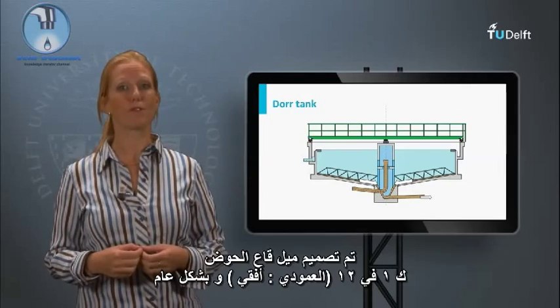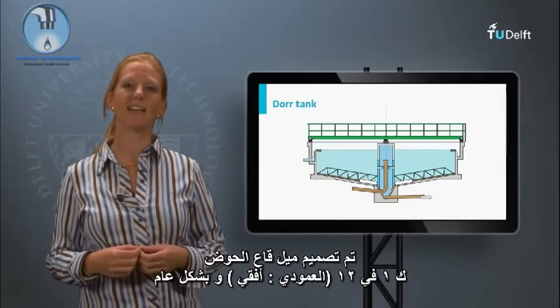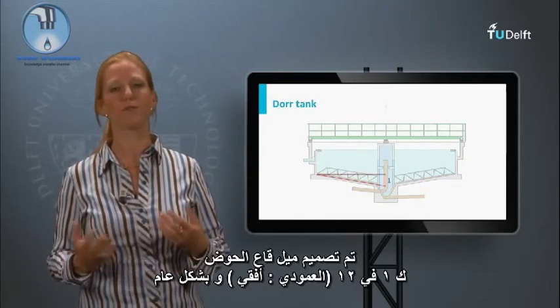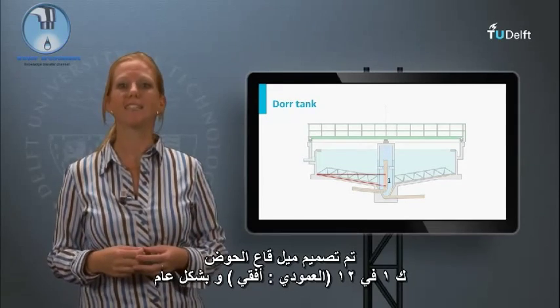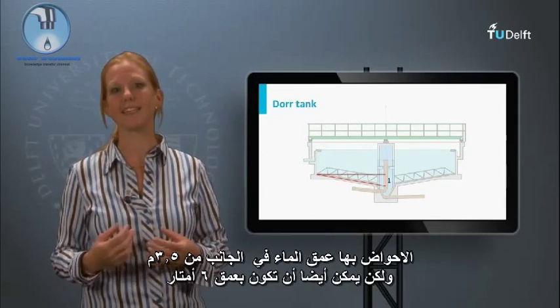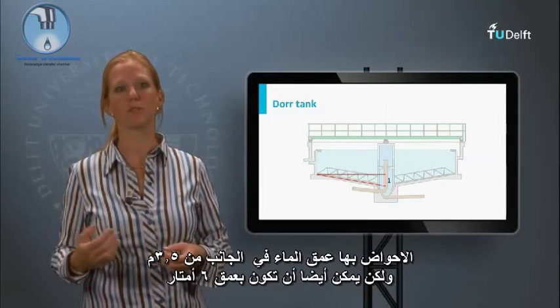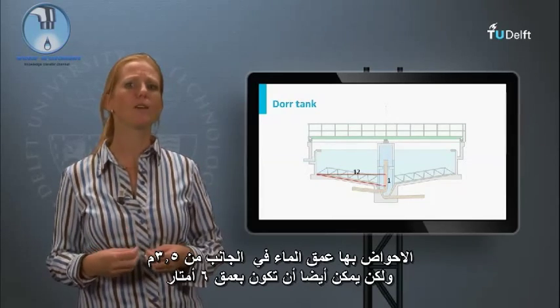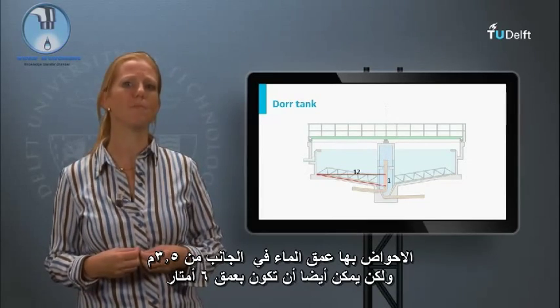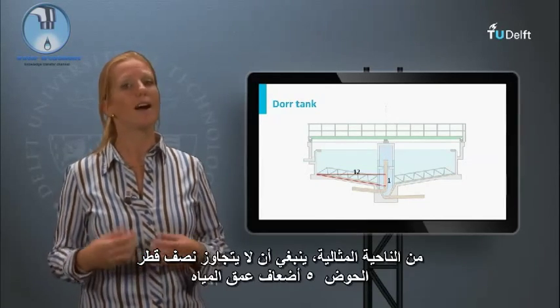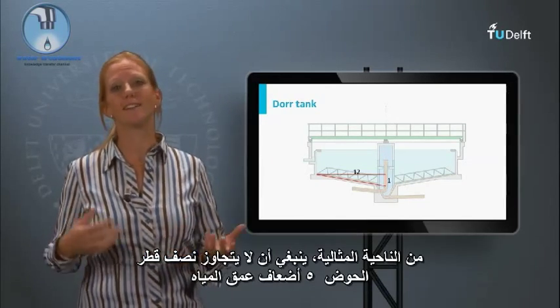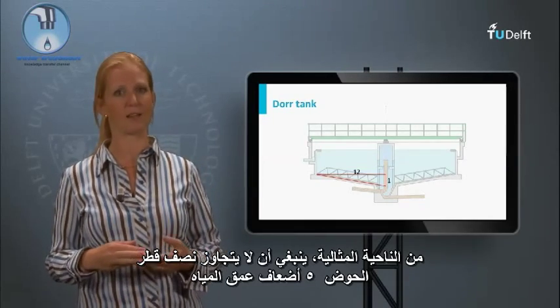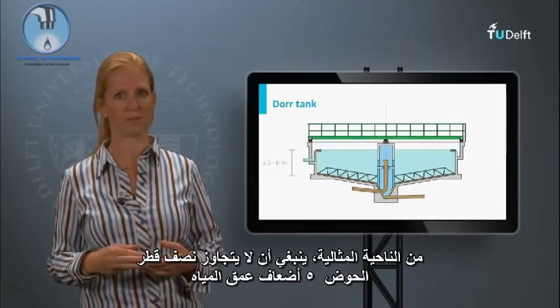The slope of the bottom of the tank is designed as 1 in 12, vertical to horizontal. In general, tanks have a side water depth of 3.5 meters, but can also be as deep as 6 meters. Ideally, the tank radius should not exceed 5 times the water depth.